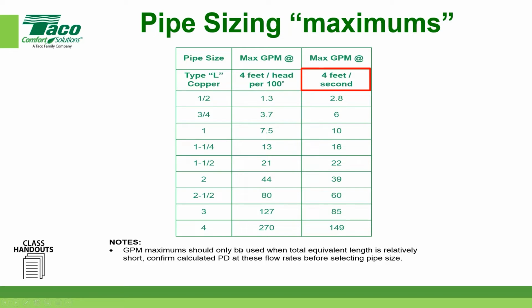Always read the fine notes down here. If you use the maximums, it gives you no wiggle room. What I'd like to say is, if you need to use, for instance, 10 gallons a minute for this piece of 1 inch pipe, make sure that 1 inch pipe is nice and short. Because if that run is all the way across the building and back, by maxing out the velocity the end result will be a whole lot of pressure drop. So you will be using the proverbial BOSFAC. What's a BOSFAC? That's a big one size fits all circulator.